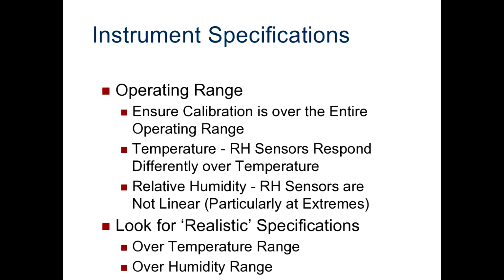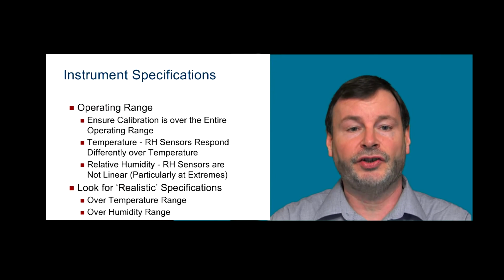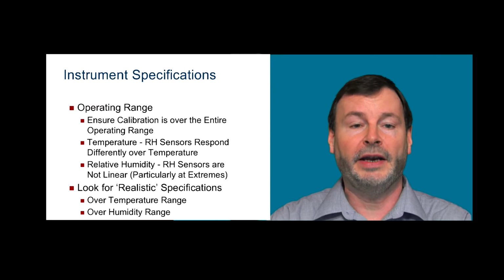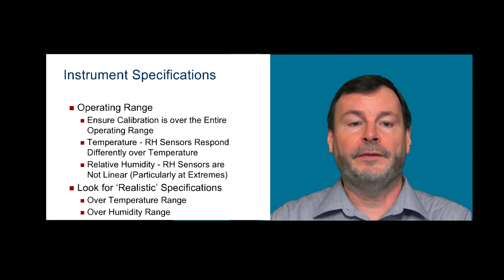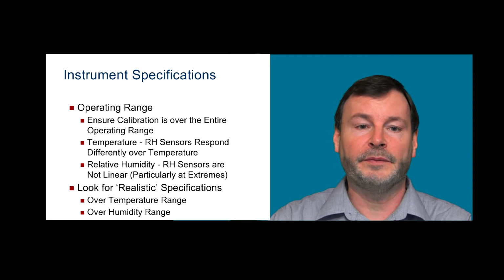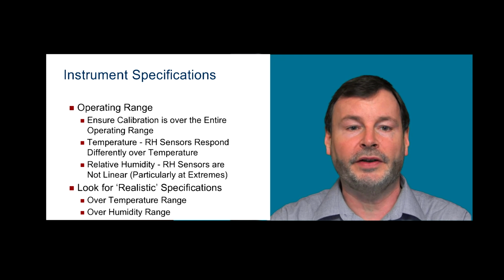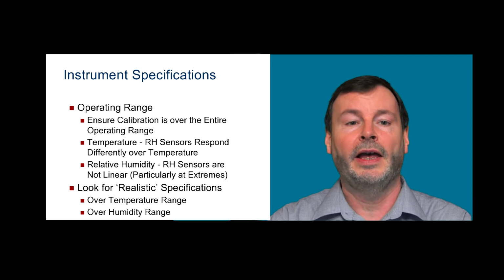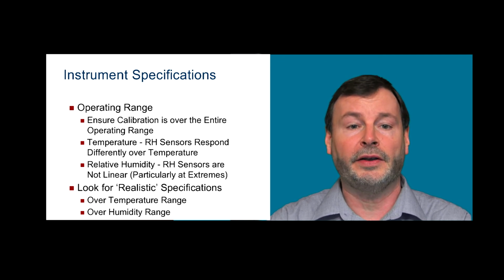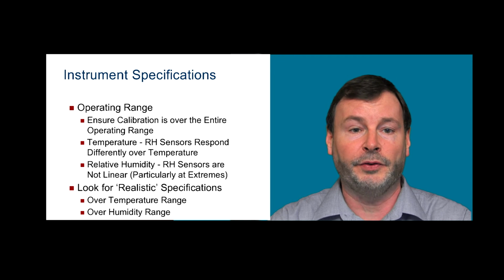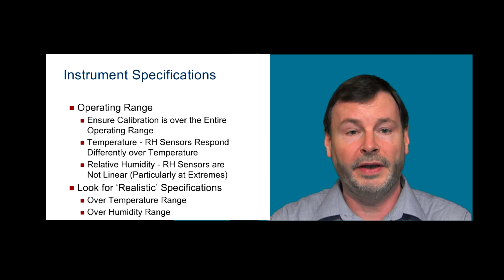And it's important to look for realistic product specifications. If a specification looks too good to be true, it probably is. If a product is specified from 0 to 100% relative humidity at 2% over the whole range, that may be unrealistic, same as with temperature. One should expect differing humidity accuracy values over a wide temperature and humidity range.